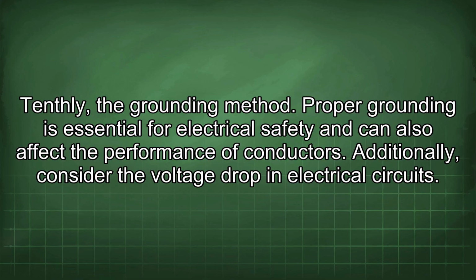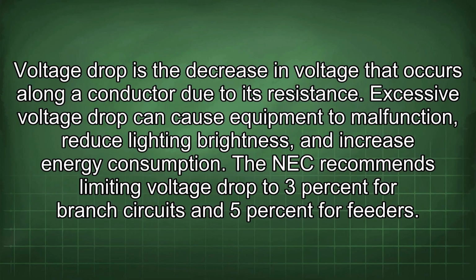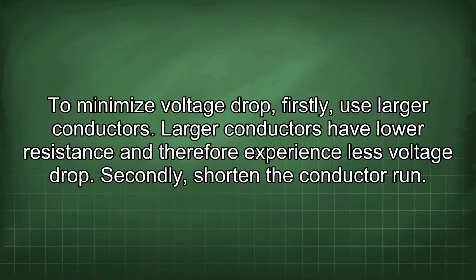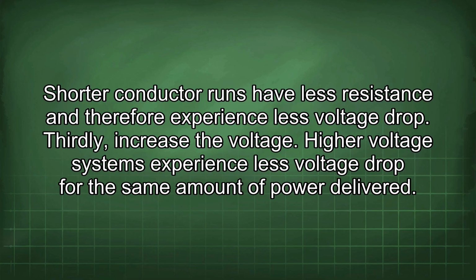Additionally, consider the voltage drop in electrical circuits. Voltage drop is the decrease in voltage that occurs along a conductor due to its resistance. Excessive voltage drop can cause equipment to malfunction, reduce lighting brightness, and increase energy consumption. The NEC recommends limiting voltage drop to 3% for branch circuits and 5% for feeders. To minimize voltage drop, firstly, use larger conductors. Larger conductors have lower resistance and therefore experience less voltage drop. Secondly, shorten the conductor run. Shorter conductor runs have less resistance and therefore experience less voltage drop.